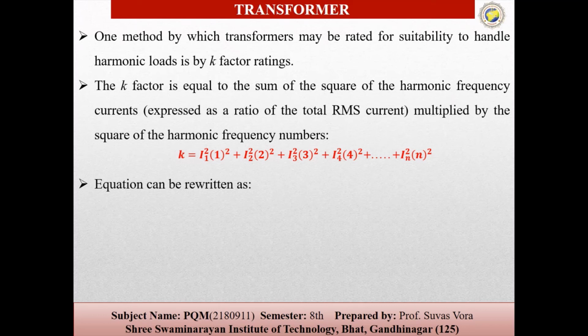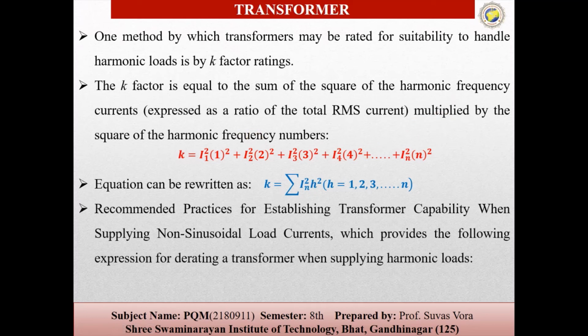Now these equations we can modify as K equal to sigma In square h square. Here In is the total RMS current and h square is the multiple of the square of harmonic frequencies. So the recommended practice for establishing the transformer capability, when supplying non-sinusoidal current, provides the expression like this.